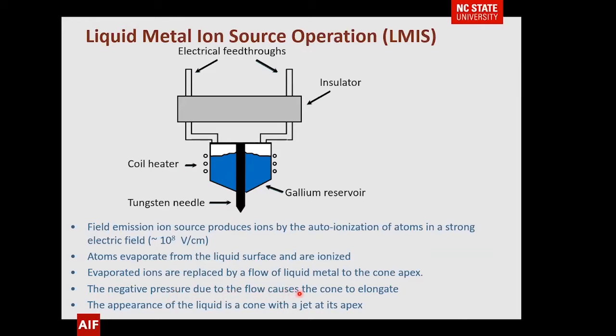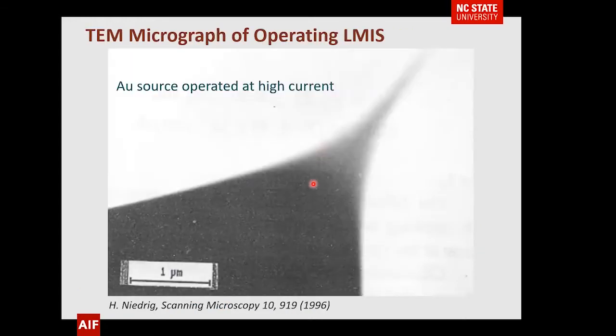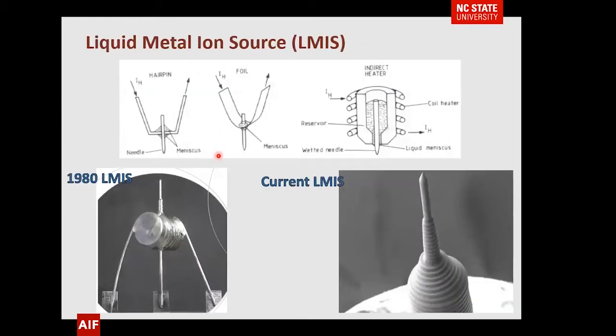This pressure due to the flow causes the cone to elongate, and what you get is a cone with a jet at its apex. Here's a TEM image of an operating liquid metal ion source. Here would be your underlying tungsten, and the gallium would wet the surface of that — you see it being pulled out. This is what enables you to obtain a very highly focused ion beam. Over time these sources have been developed into something quite small with a 1500-hour lifetime.